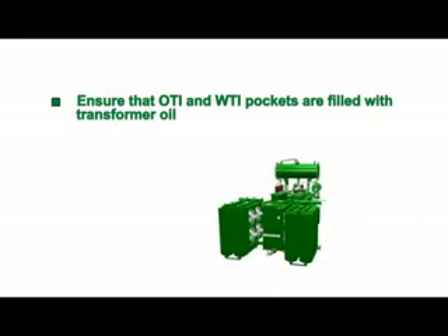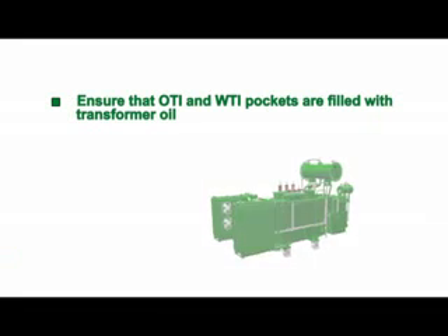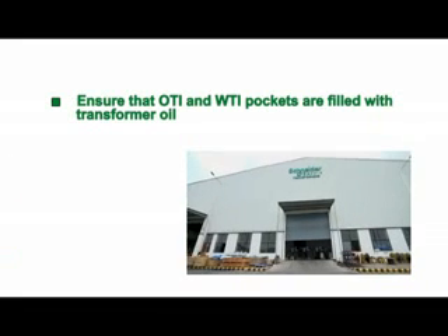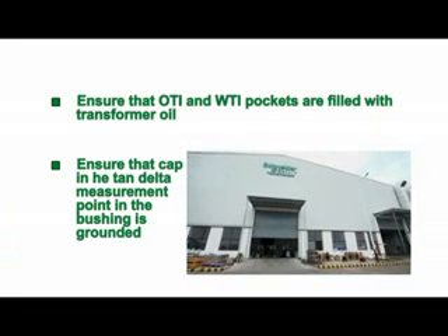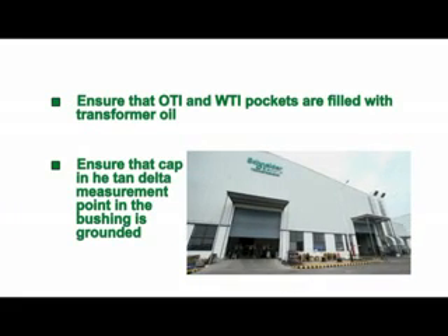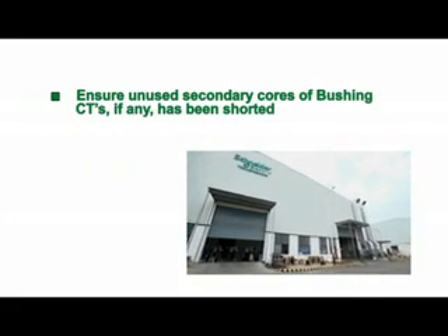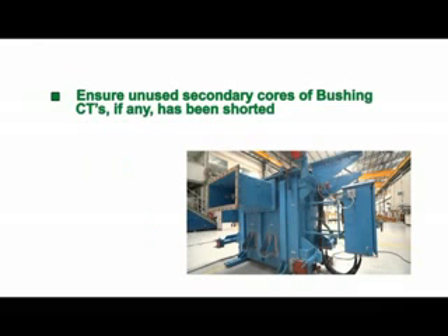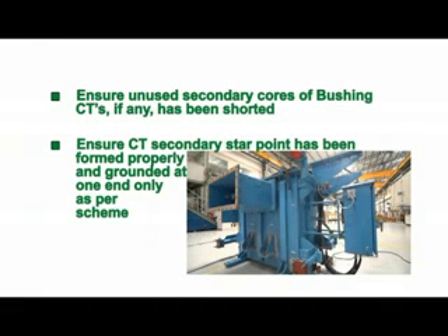Ensure that OTI and WTI pockets are filled with transformer oil. Ensure that the cap in the tan delta measurement point in the bushing is grounded. Ensure unused secondary cores of bushing CTs, if any, have been shorted. Ensure the CT secondary star point has been formed properly and grounded at one end only as per scheme.